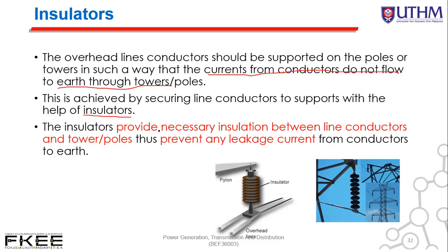Okay, the insulator provides necessary insulation between line conductor and tower pole to prevent any leakage current from conductor to the earth. Okay, this is the example of the insulator. Let's say this is the overhead line or the conductor. So this is the cross arm. So insulator will protect the current flow from the conductor to the cross arm or to the tower. Okay.